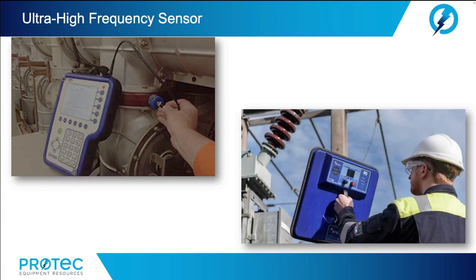Let's start with ultra-high frequency or UHF sensors. Now, every time a partial discharge event occurs, electromagnetic waves are transmitted from the site of the defect. This emission may also be called RFI or EMI, radio frequency interference or electromagnetic interference. The partial discharge emission is a broadband electromagnetic emission which can range from the upper radio frequency range up into the microwave range. The UHF range from 300 MHz to 1500 MHz is a typical bandwidth to probe for partial discharge defects in medium and high voltage power systems.